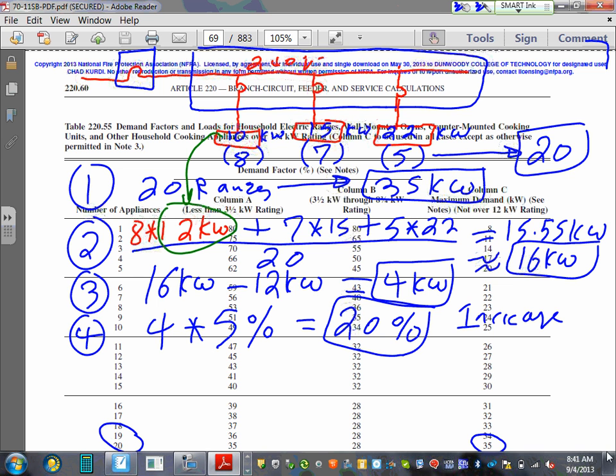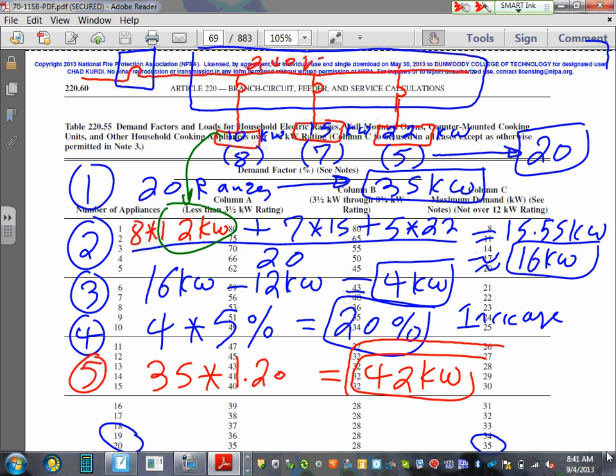The last step, step number 5, is you take the demand. What was your demand to start with, gentlemen and ladies? 35. Here's my demand, 35. Increase the demand 20%. How do you increase the number 20%? Multiply that number by 1.20. Can somebody do 35 multiplied by 1.20, please? 42 kW. The demand for this system is 42 kW.